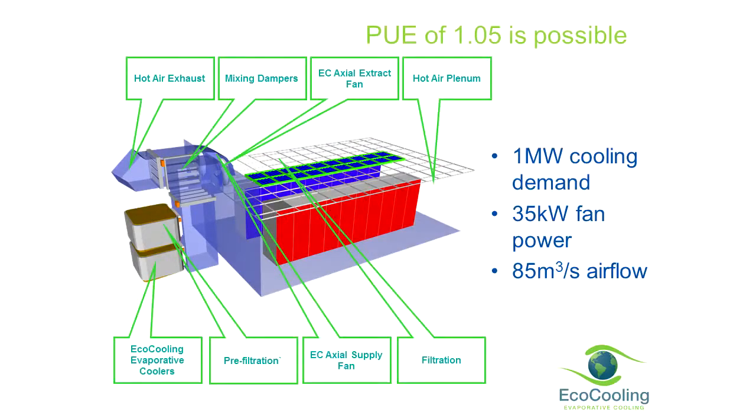So then it all comes down to the actual stakeholders and their balance on their risk assessment of how much money they want to save. As a rule of thumb, you're going to use about 35 kilowatts for every meg of installed load. That's your target. The previous company, CGG, they've tried everything. They've got servers in oil baths in Houston and everything. For them, a PUE of 1.3 is just the standard. If you're above 1.3, you're a poor performer in their organisation. So another benchmark that people need to start thinking about in terms of their operational performance.